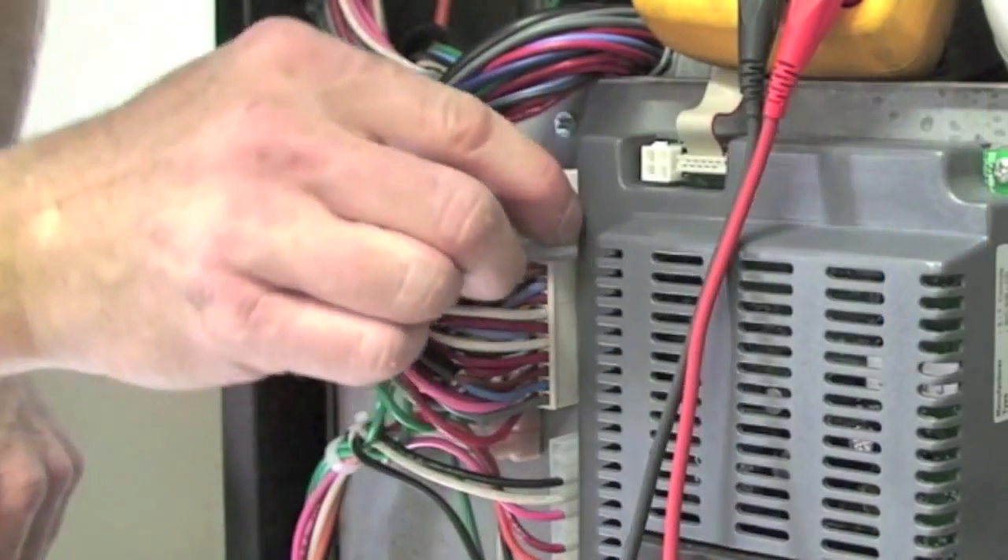If it does not match, check wiring into connectors to assure that there is not a loose connection. If the wiring connections and the sensor are okay, you will have to replace the control.